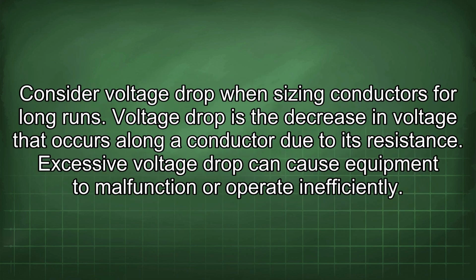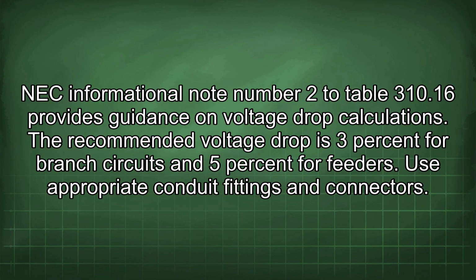Consider voltage drop when sizing conductors for long runs. Voltage drop is the decrease in voltage that occurs along a conductor due to its resistance. Excessive voltage drop can cause equipment to malfunction or operate inefficiently. NEC Informational Note Number 2 to Table 310.16 provides guidance on voltage drop calculations. The recommended voltage drop is 3% for branch circuits and 5% for feeders.